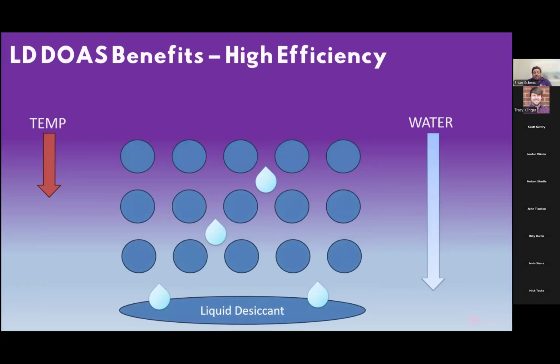So let's talk about the other benefit of Mojave's liquid desiccant system, and that is ultra high efficiency. As I mentioned before, if we don't have to drive the temperature down as far to remove as much moisture, we are saving energy. Every line of enthalpy on the psychrometric chart that you cross over is exponentially more energy intensive. So to go from 60 to 59 takes less energy, less cost than to go from 59 to 58, right? So every line you cross over is exponentially more energy intensive. So the fewer lines of enthalpy we have to cross, the better.